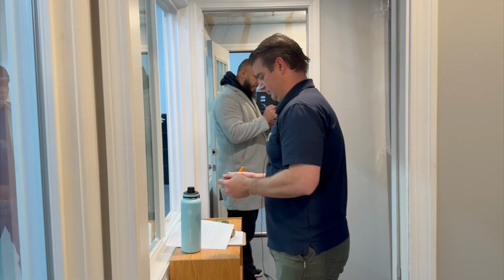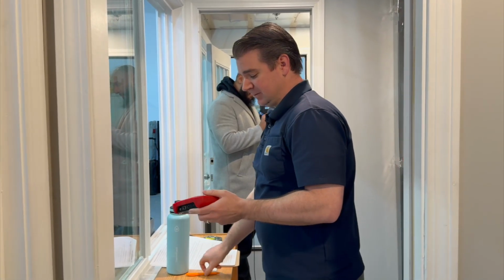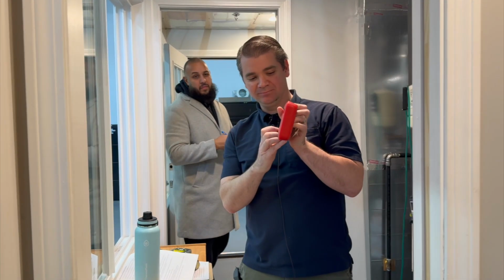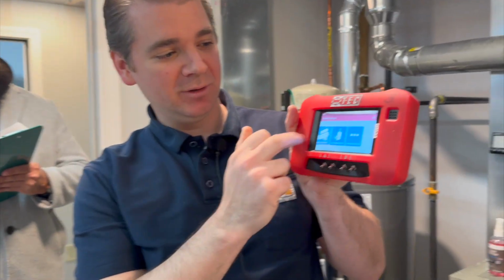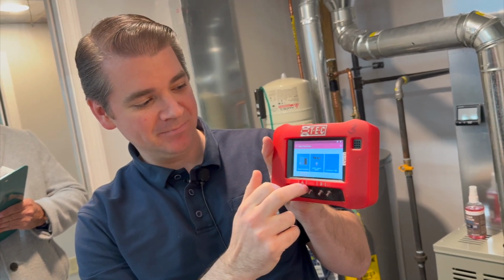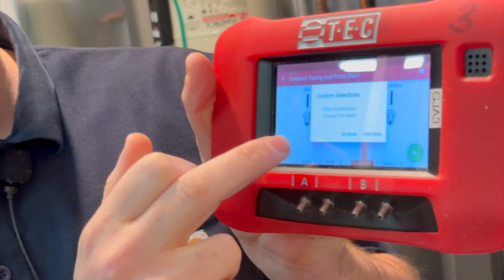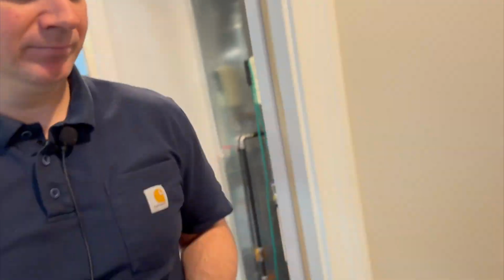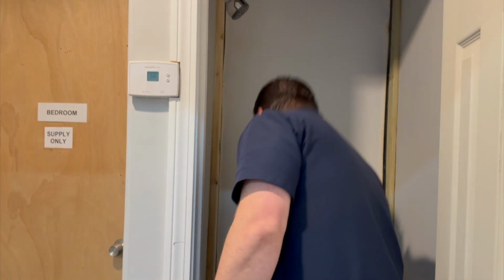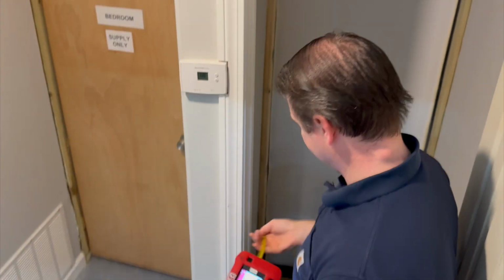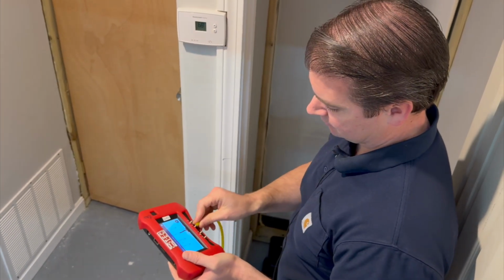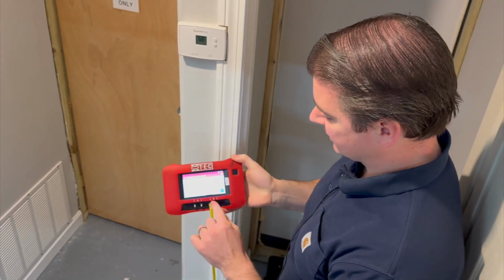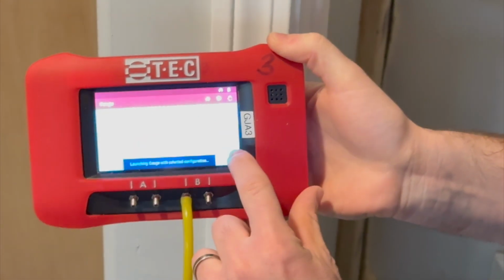And then measure the flow rate of one local exhaust ventilation fan. Turn my manometer on. I'm going to go to tubing assistant. I'm going to scroll all the way over to the right, other applications, exhaust fan meter. It tells me how to set up my hose. Hit continue. I'll go over to the bathroom. Turn the fan on. Make sure my hose is set up correctly for the manometer. Hit the play button. That sounded expensive.